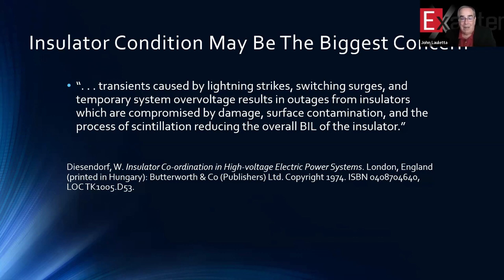So now you don't know where the problem is, and the lineman will mark, unknown cause of the trip. Well, the issue here is that event, that high energy event, has damaged the surface of the insulator and its hydrophobicity. So now it's going to be more apt to collect dry bands again. So this is a problem that's going to recreate itself over and over again, and it's not gone. It just temporarily healed itself, if you will.